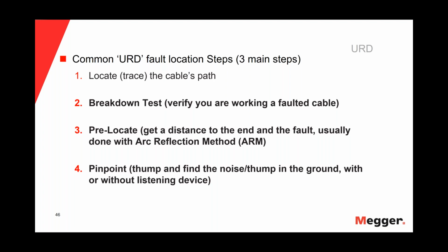I know Henning mentioned ICE. There was a mention of decay. There are other ways to get pre-location distances, but in the URD world, most of the fault location is going to be done with the arc reflection method. And that's why I call it a distance meter. Obviously it's an impedance measuring device, but what we're interested in is how far away the fault is.